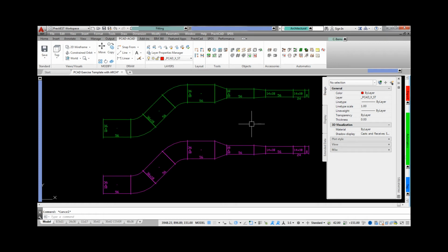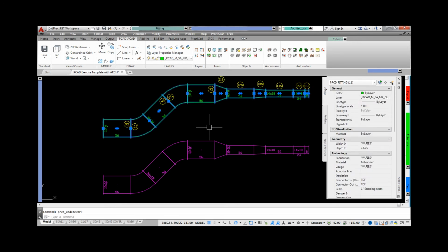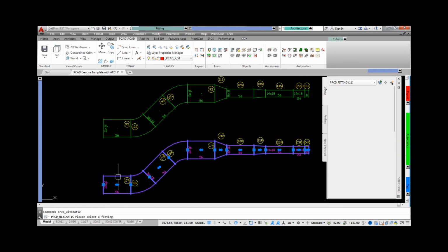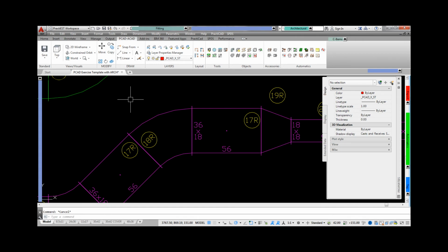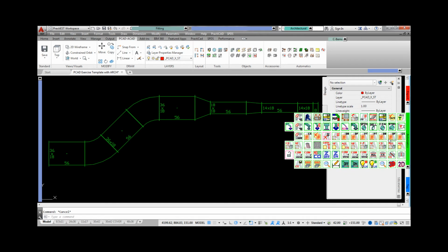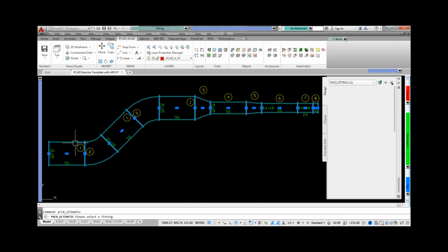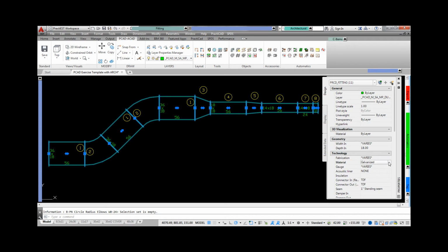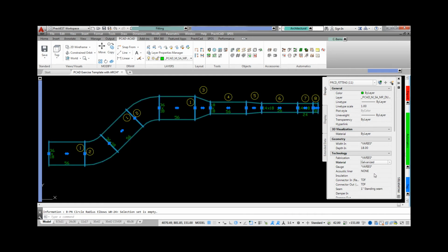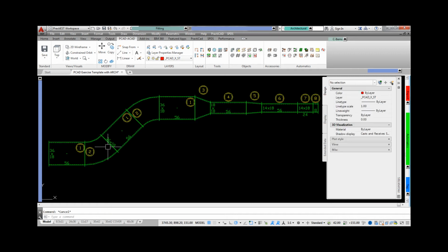And remember, since we have logic-driven tags, we can do logic-driven numbering as well. For example, notice here as we piece number this supply run up top, the tags show 9S or 10S for supply. But when we number the bottom return line, the numbers show 9R or 10R for return. These will even change as we edit the drawing later. You may also notice the option for identical fittings, identical fitting numbers. Lastly, we have a situation where a user wanted to auto piece number but wanted the border of the numbers to change based on material. Galvanized got a circle border. When we added the material later to aluminum, it got a square border. Then a hexagon for black iron, and lastly they had a circle inside a circle for lined duct. All of this can be automated through our advanced numbering automatics, always making sure you get the right number in the right place.